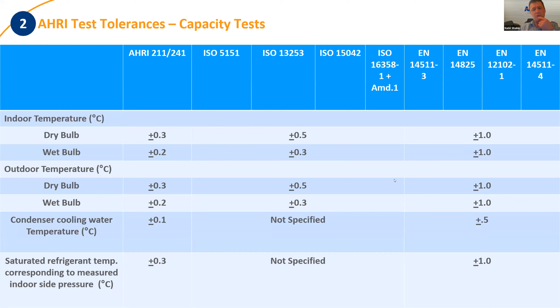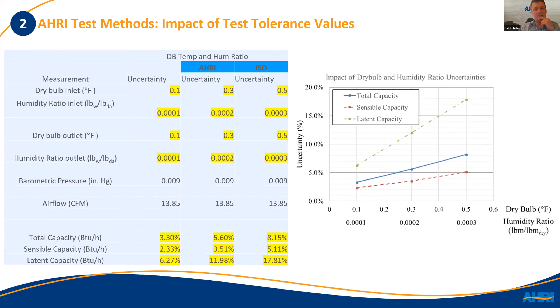Because we have done a study to compare tolerances when you test in a psychrometric test room or a lab. The higher the variation is, the bigger the chance that the result will also vary by wider ranges. So your total capacity can vary up to 8% if you allow 0.5 tolerance, versus 5% or less if you use AHRI standards. This is a big percentage and can sway your savings a lot.